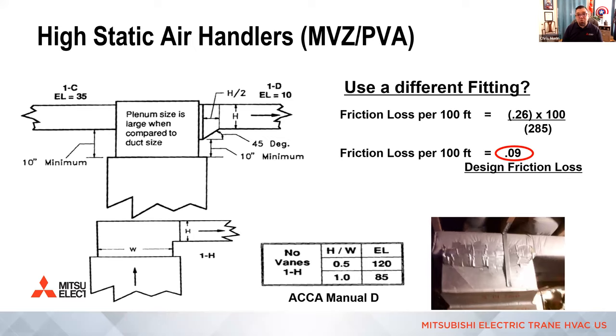So really important, instead of using that nice, easy transition, and hopefully you can see my pointer here, the 1D fitting, that's a nice tapered fitting going into your trunk off the plenum, that's a 10-foot fitting. If instead you use what's pictured in the bottom right here, which would be a bullhead T. And we see this a lot with newer construction homes, not on purpose, right? Where on a new construction home, they might rough in the trunk and the branches before the plumber gets in or the electrician gets in and you lose all of those bays. And then once hopefully you get some sort of deposit, you come back with your equipment and you stab it into the bottom of the trunk. That becomes a bullhead T because it's not a full box.